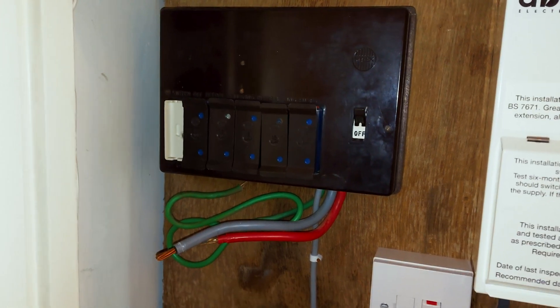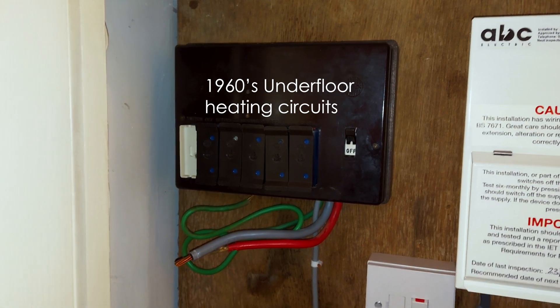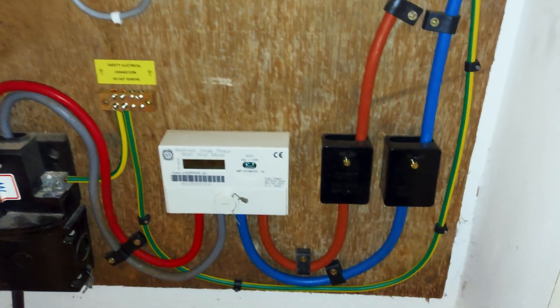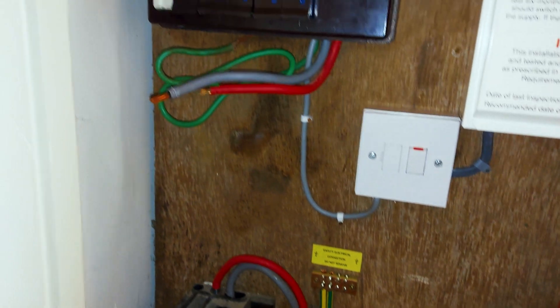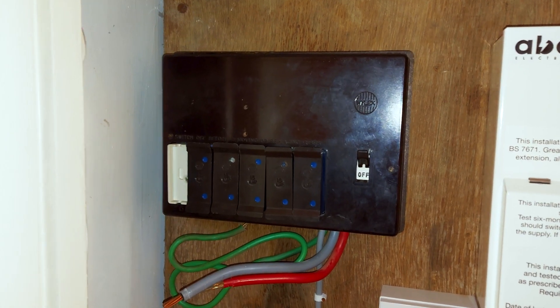Good morning, welcome to the channel. Today I'm going to be swapping out an old rewireable fuse board for an RCBO board for underfloor heating and fitting a new programmable room stat. So let's jump straight into it. That's the board there — there's five circuits and a spare way. This is a property I've been working at before, so we've got to put some new tails in down to those Henley blocks which have already been prepped up, and then we're going to put a six-way RCBO board in.